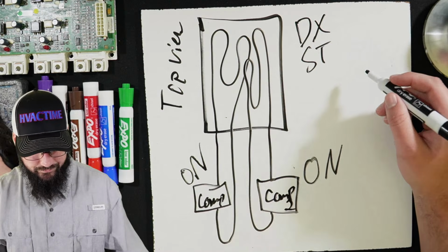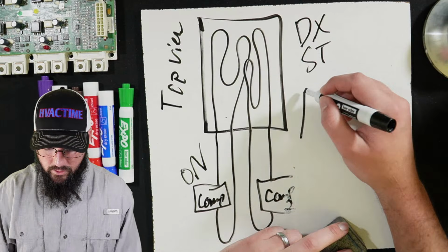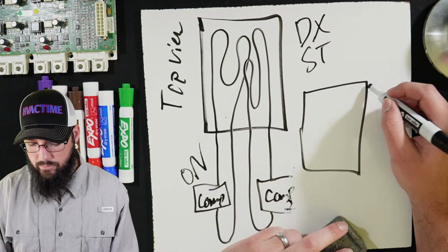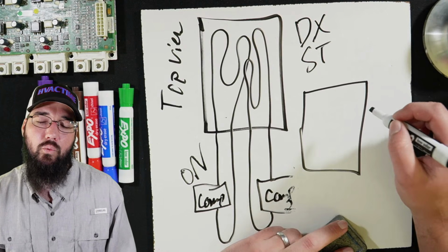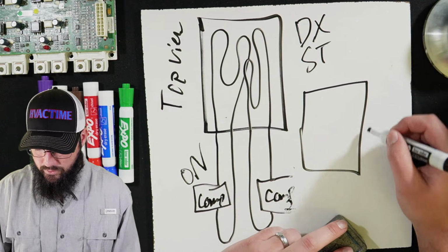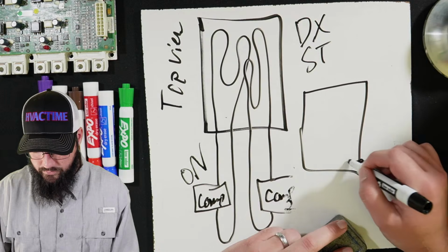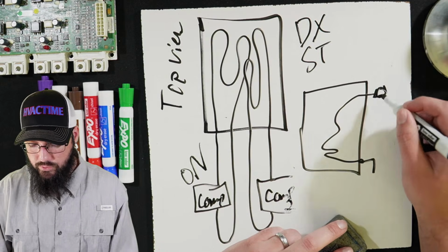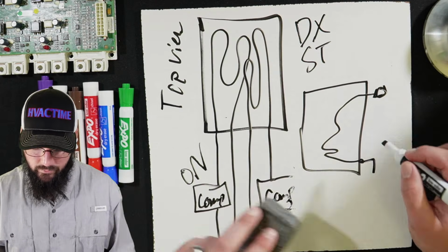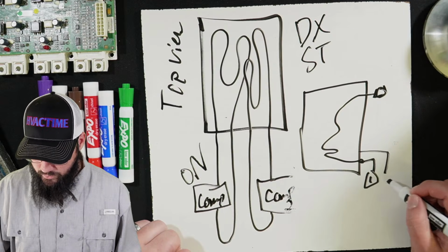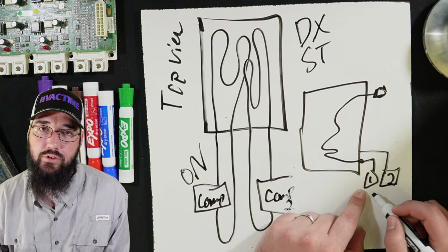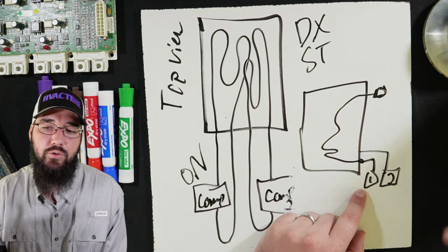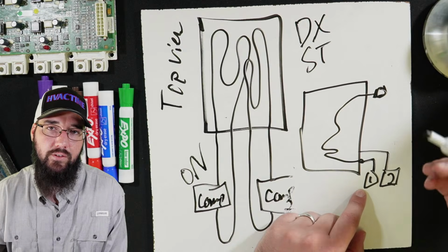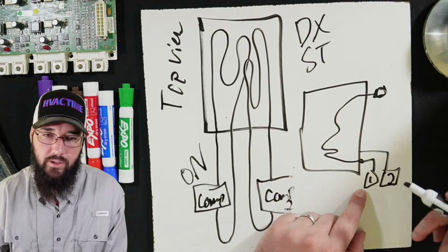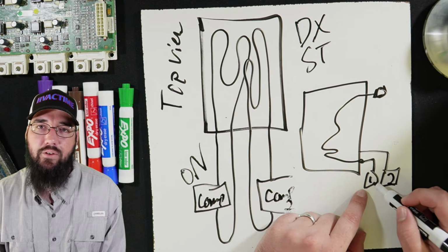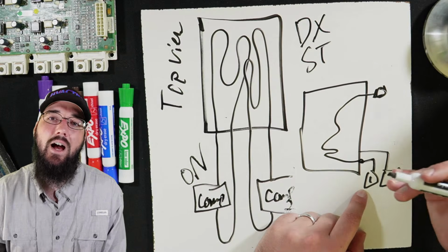All right, so in an RTU, we have our evaporator coil, and both circuits are interlaced into this coil around each other. Our metering device would be feeding in here, going through its tubes, coming out the suction line, and we've got two circuits in here total feeding into this coil. We'll say this is 1, this is 2. So when it's just circuit 1 running, trying to process this coil, let's say we're trying to achieve a supply air temperature set point, an SAT, you will see that your evaporator saturation runs higher.